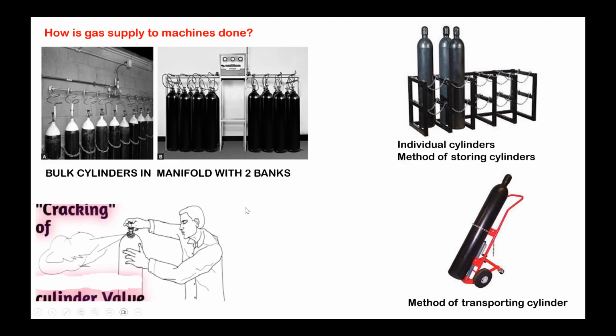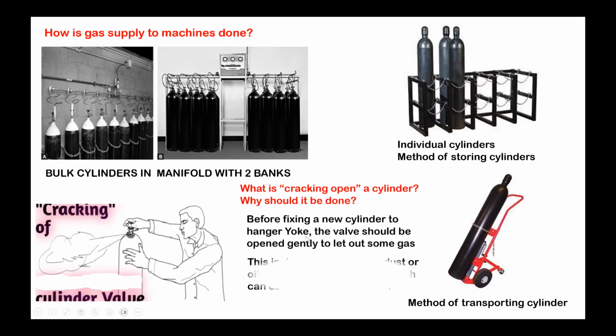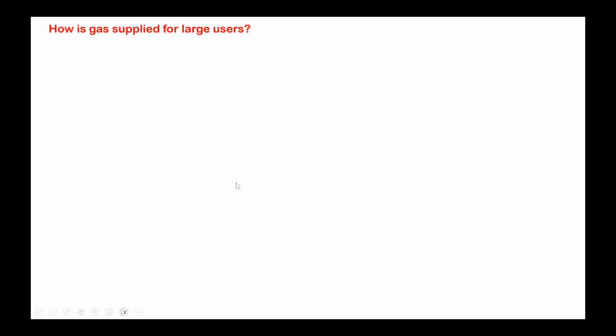This is a common thing done in the earlier days, but sometimes examiners may ask you this because you are not used to it. In our student days, we used to have the E-type cylinders fitted to the machine, and every time it got exhausted during the anesthesia itself, we would have to change it because we had a spare cylinder. We would open that, remove the empty one, and attach a new full cylinder. During that time, it is routine practice to open the cylinder before attaching it to the machine and let the gas out so that any oil or dust in the outlet is blown away, so that you will not have the problem of fire or occlusion. So if they ask you that, you must be able to answer.